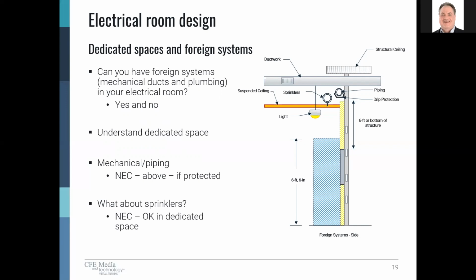You really do need to understand that dedicated space. You need to understand the height of your equipment. Panel board, switchboard, and switchgear can have vastly different heights. You need to understand where the ceiling in the room is, where the structural ceiling is. The distance is identified as 6 foot or the bottom of structure, understanding that structure is not a drop ceiling. It is the actual structural ceiling in the room. So once you understand that dedicated space and the height, you understand that if you're above the 6 foot or to bottom of structure, you can put mechanical and electrical piping in if protected.